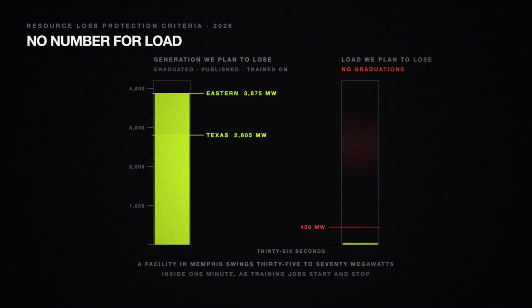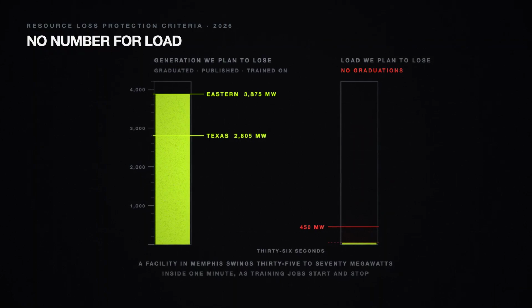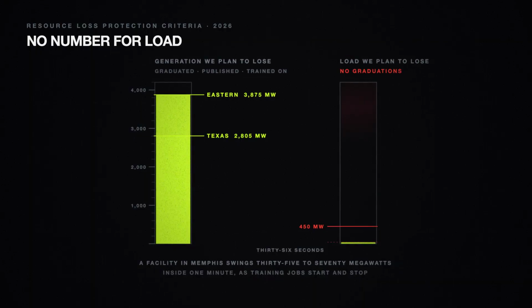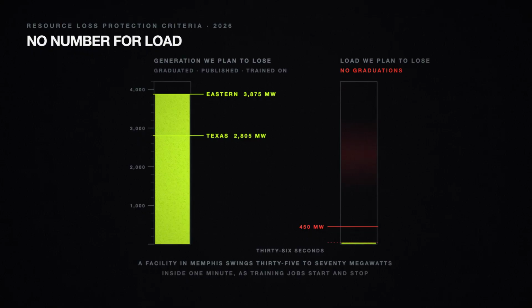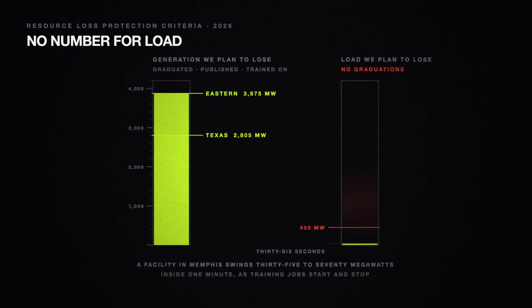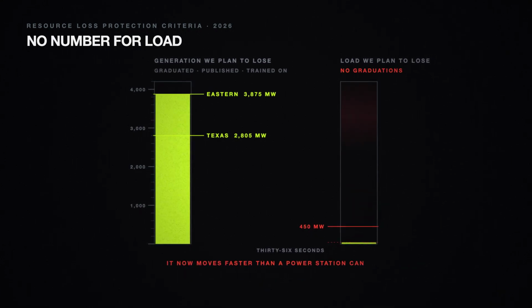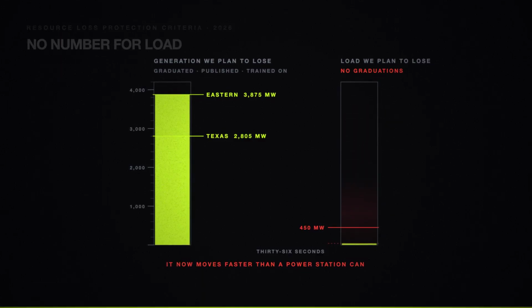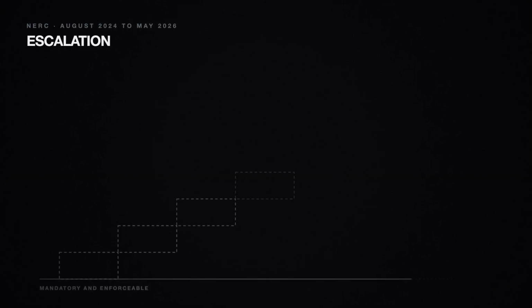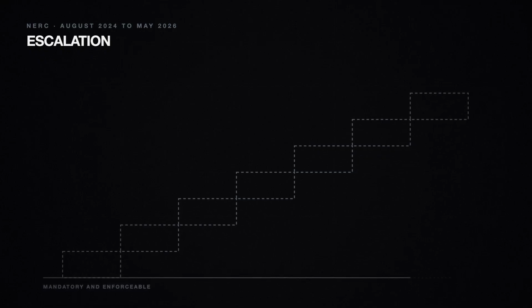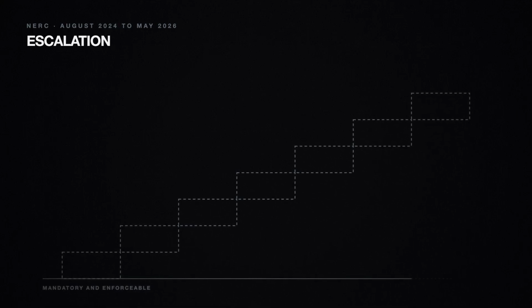A single facility in Memphis swings between 35 and 70 megawatts inside a minute, as training jobs start and stop. Another North American data center went from 450 megawatts to 40 in 36 seconds, sat there for 4 hours and came back. The thing that behaved slowly now moves faster than a power station can. The organization responsible for reliability across North America noticed. What happened next is worth watching closely, because the shape of it tells you more than any single document.